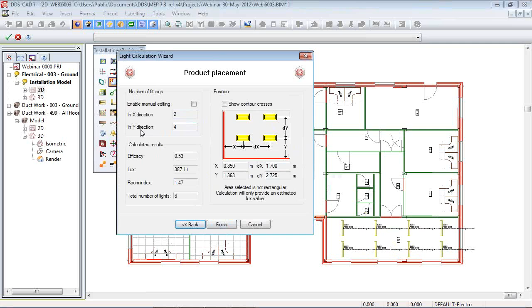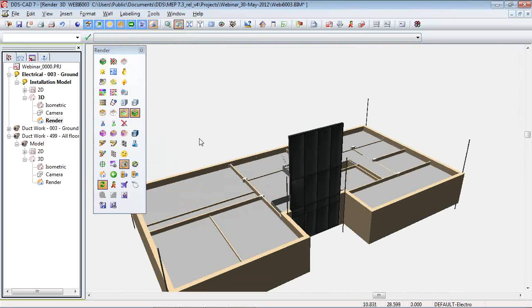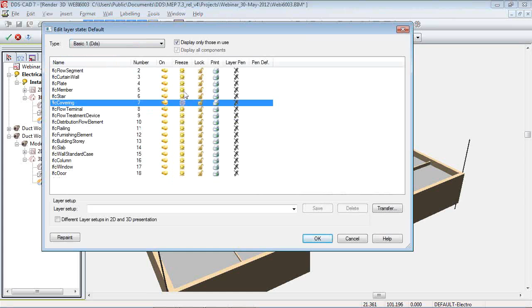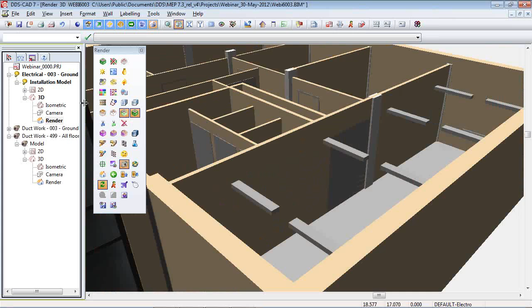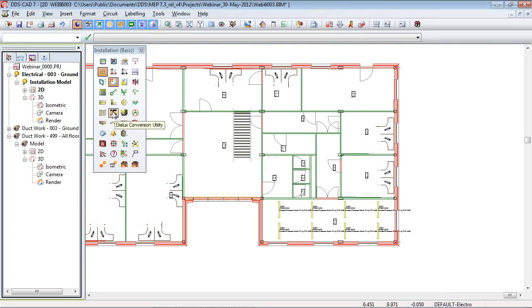Within DDS we have an internal light calculation function in which we can pick a specific room and say, okay, this canteen would be recognized with a reflex factor and also a maintenance factor like a clean area. Based on the light fitting we are putting in, like a 2x36 tube light, DDS is proposing that we will have an orientation the other way around, or like this. Then we will have 2x4 light fittings for this specific room.